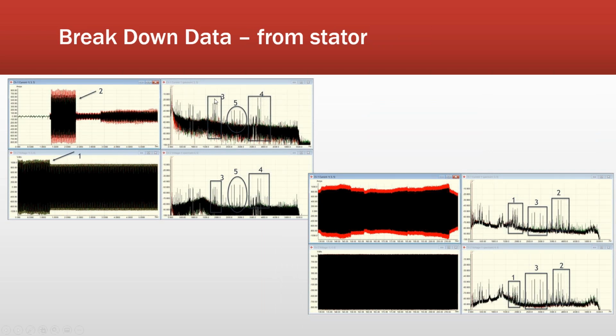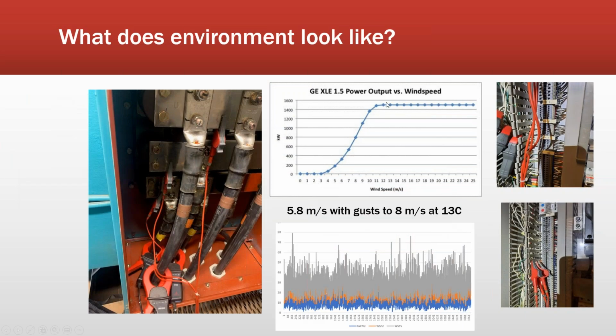When I see readings this high, that usually means there's going to be a resonance. You'll notice that it's in both voltage and current. And you notice I'm looking at both. Why would I look at both? Generators are voltage, right? Well, the reason I look at both is because of this power curve.